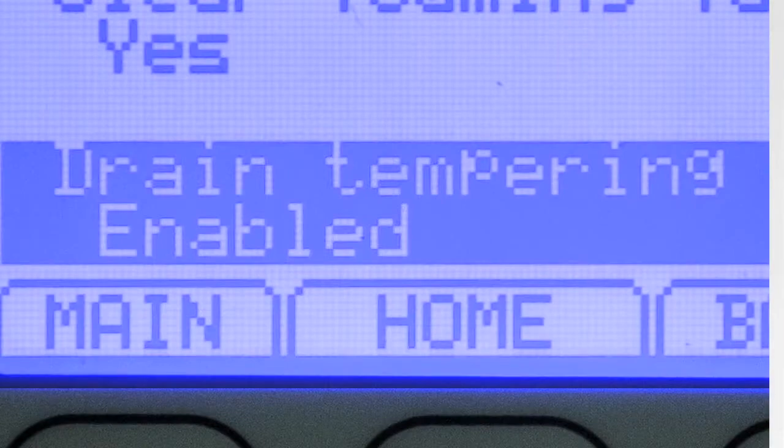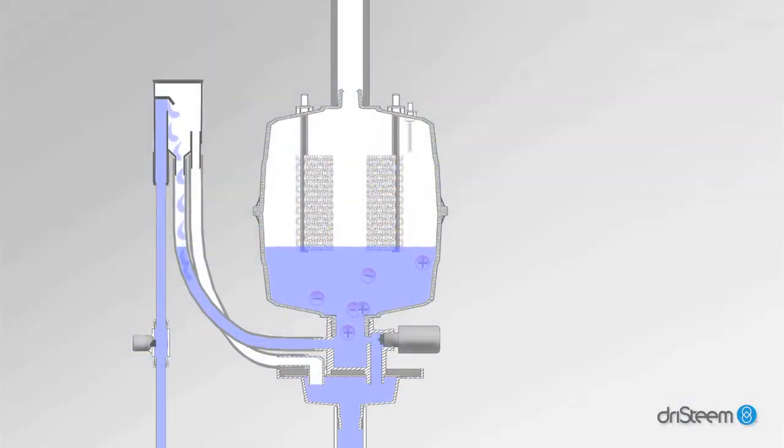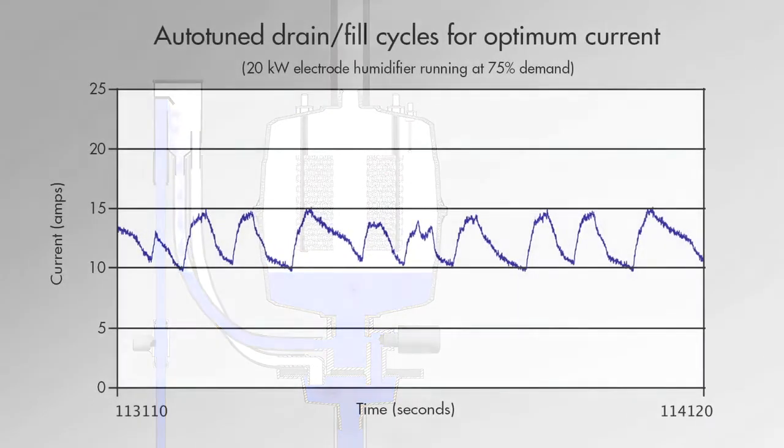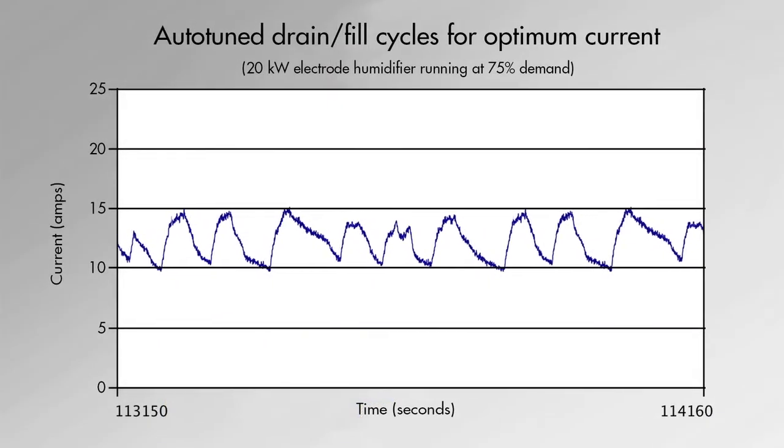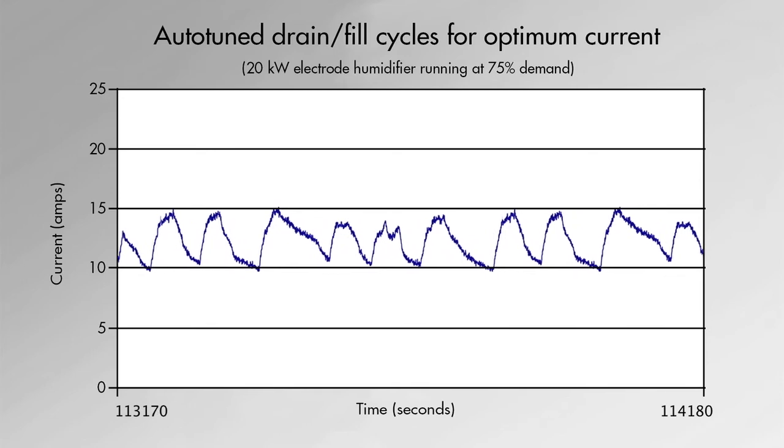DriSteem electrode humidifiers can cool their own drain water by opening the fill and drain valve simultaneously, and a proprietary controller algorithm monitors water conductivity and automatically tunes drain and fill cycles to keep electrical current within optimum parameters.